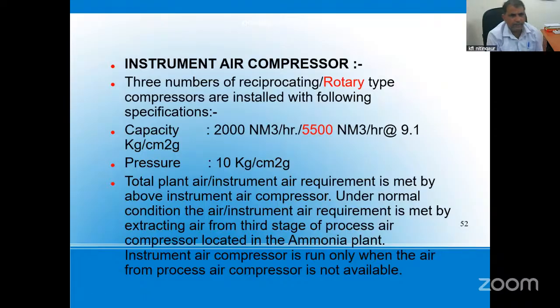Now the instrument air compressor. The instrument air compressor is used to compress the air. But the compressed instrument air has moisture inside it, which is not suitable to operate a control valve. Our plant has a number of control valves, because in a heated area man cannot operate a valve, and due to automation all the control valves are operated through air to open, air to close.